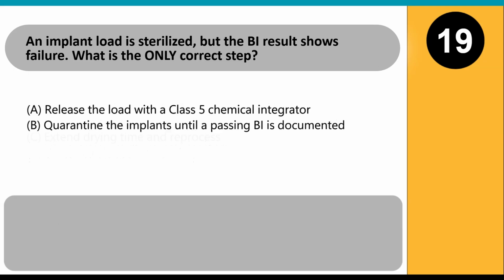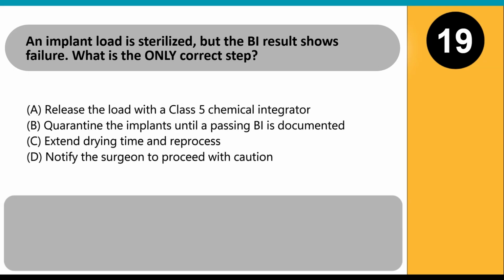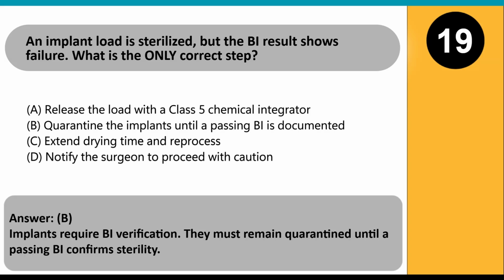An implant load is sterilized, but the BI result shows failure. What is the only correct step? A. Release the load with a Class 5 chemical integrator. B. Quarantine the implants until a passing BI is documented. C. Extend drying time and reprocess. D. Notify the surgeon to proceed with caution. Answer: B. Implants require BI verification. They must remain quarantined until a passing BI confirms sterility.